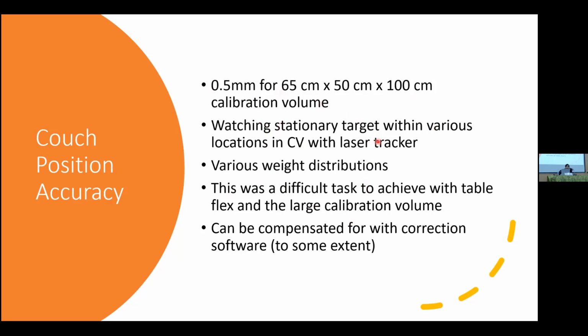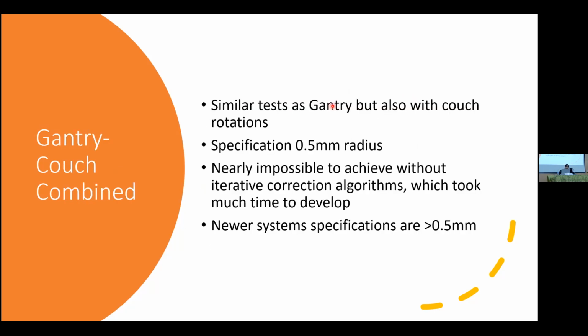And the vendor may want a very small calibration volume because it's easier for them. But if it's very small, then what happens when you're outside of that, particularly doing these craniospinals, these long treatment fields? So 100 centimeters, that's a meter. That's a pretty good size. But I've seen some where they try to say their calibration volume is actually much smaller, like 50 by 50 by 50, right? That's just too crazy small.